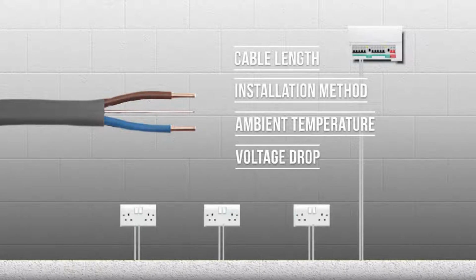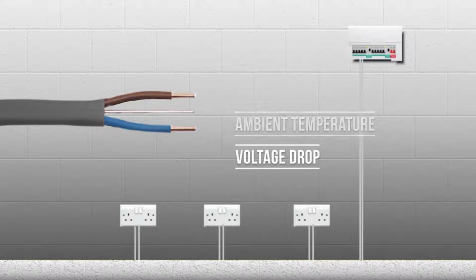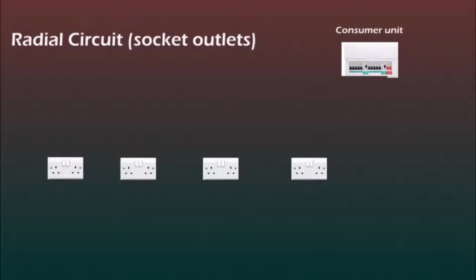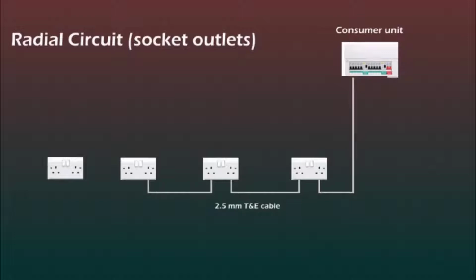Instead, I'd like to simply explain the construction of each circuit and what is the recommended size of cable and MCB for each one of these circuits. You can also find this information in a consumer unit, and we've got 4 socket outlets on this circuit. So the 2.5 twin-earth cable goes from consumer unit to the first socket outlet, and then from the first to the second, and so on, and it finishes at the last socket outlet. The MCB for this radial circuit should be 20 amp.